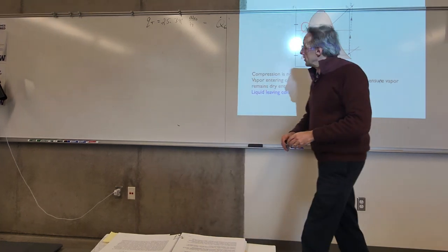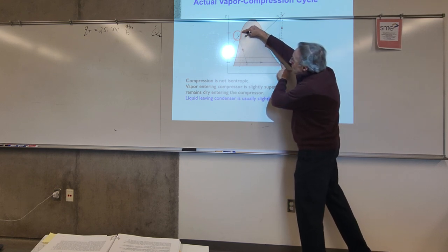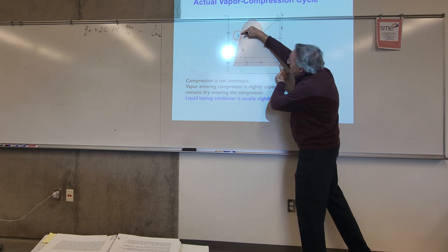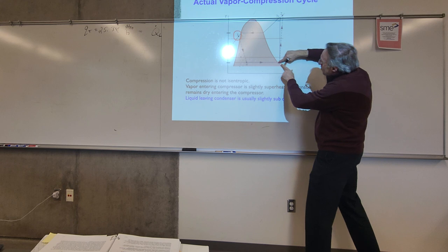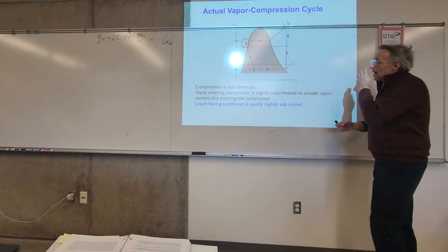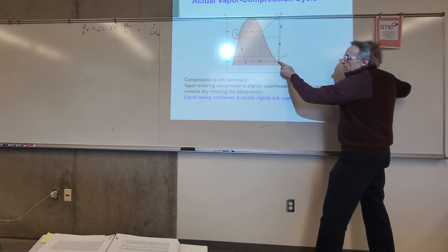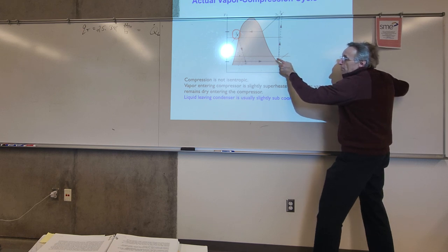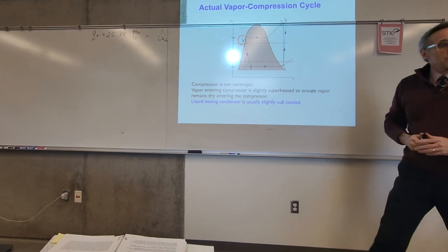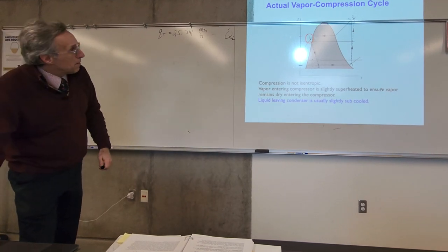Now, a way that you can achieve this simultaneously is you bring these two streams into contact. You bring the condensate outlet, saturated liquid, and you run this tube of refrigerant beside the tube coming out of the evaporator. You allow them to physically contact each other, and because this is hot, heat transfers from the hot condensate to the vapor coming off the evaporator, resulting in superheating of the vapor and subcooling of the liquid. So that's one way this is done, by putting the tubes side by side and then wrapping common insulation around them, binding them together.